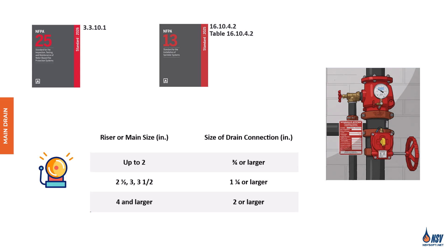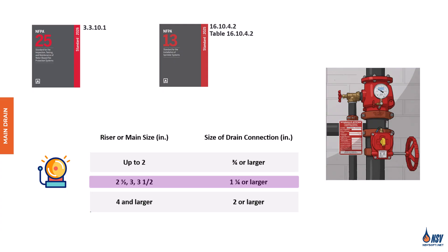For risers or mains up to 2 inches, the required drain connection size is three-quarters inch or larger. For pipe sizes 2 and a half inches, 3 inches, and 3 and a half inches, the drain connection must be at least 1 and a quarter inches. And for risers or mains 4 inches and larger, the drain connection must be 2 inches or larger.